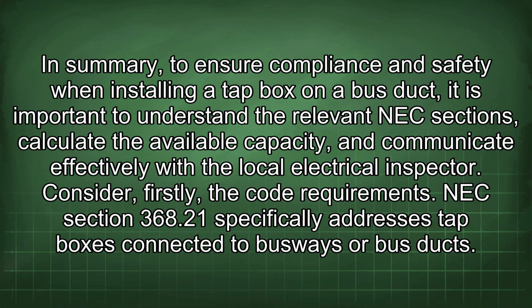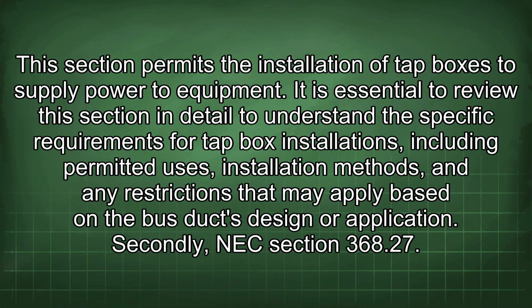NEC Section 368.21 specifically addresses tap boxes connected to busways or bus ducts. This section permits the installation of tap boxes to supply power to equipment. It is essential to review this section in detail to understand the specific requirements for tap box installations, including permitted uses, installation methods, and any restrictions that may apply based on the bus duct's design or application.